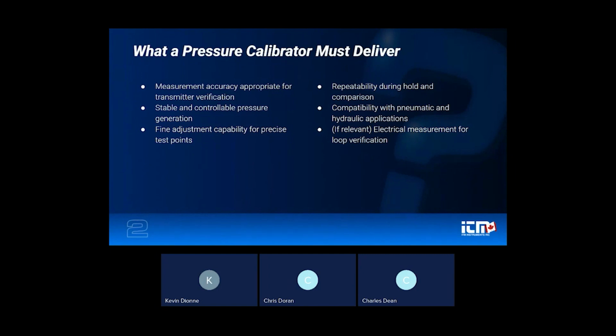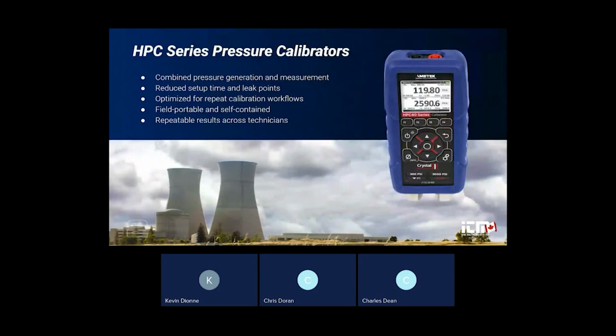So when these elements are all combined, controlled pressure generation, stable reference measurement, proper accuracy, and repeatability, the result is a self-contained tool capable of supporting pressure calibration without sacrificing your measurement integrity. An example of this tool, up to this point, you've seen the Crystal XP3i. This tool on the screen, which you saw in the last two slides, is an example of the HPC series by Crystal. It integrates pressure generation and pressure measurement into a single handheld platform. It's available in both pneumatic and hydraulic configurations. It's built for field verification and calibration work. It's portable, it's affordable, and it's a great instrument for what we just covered.